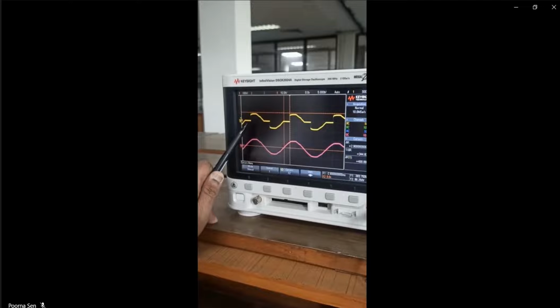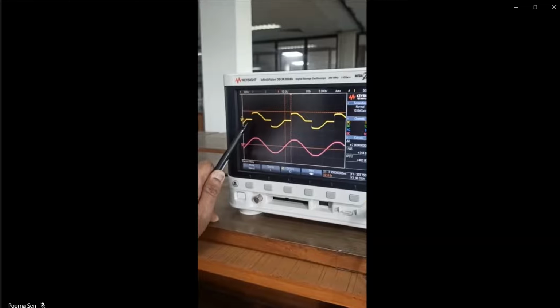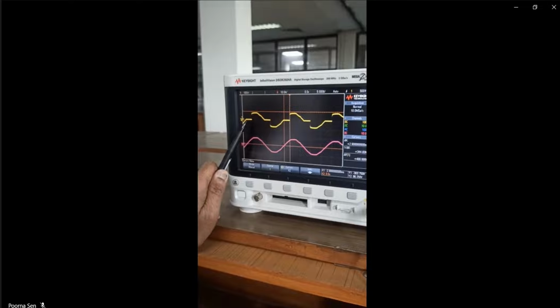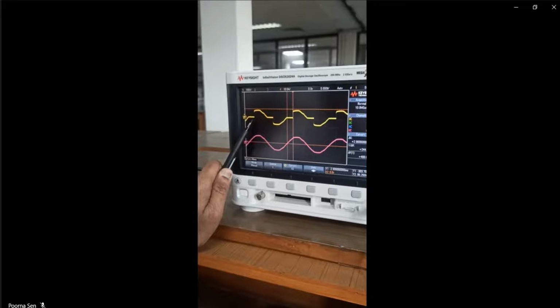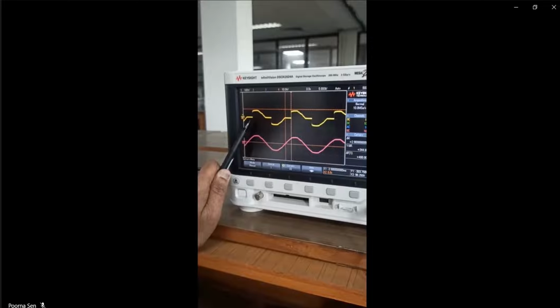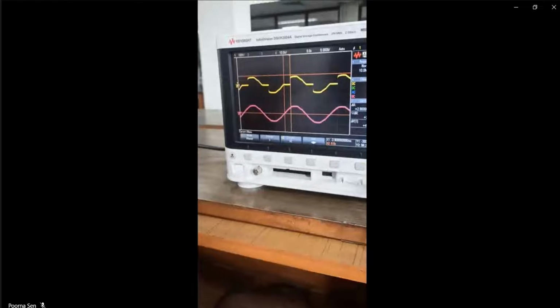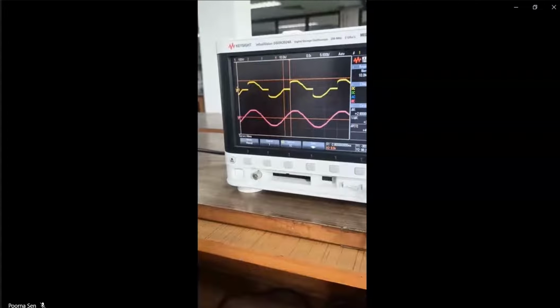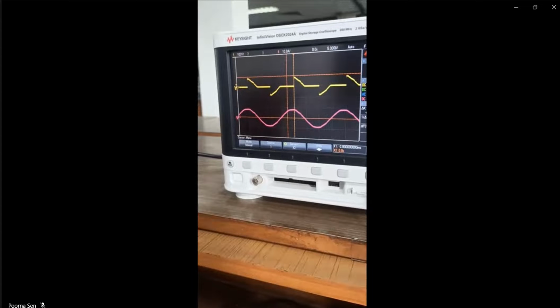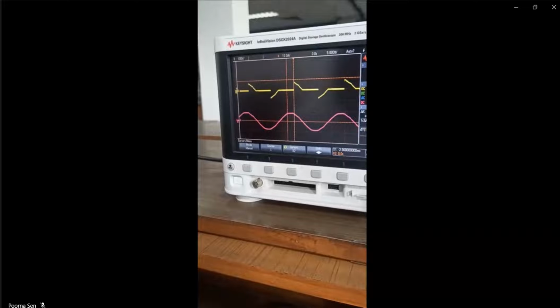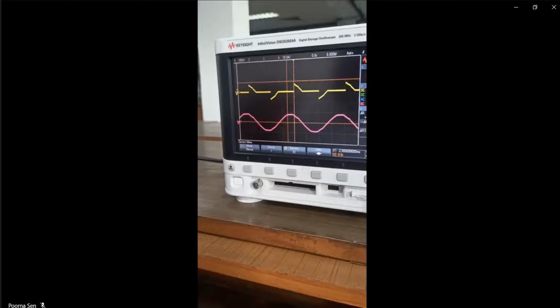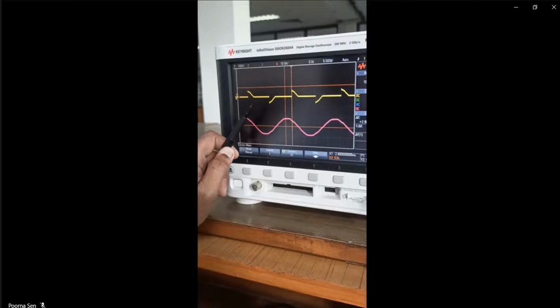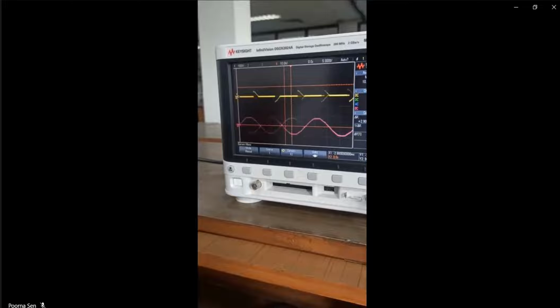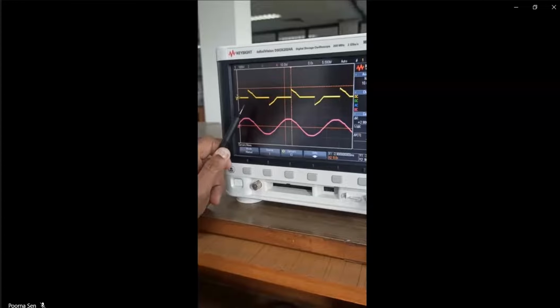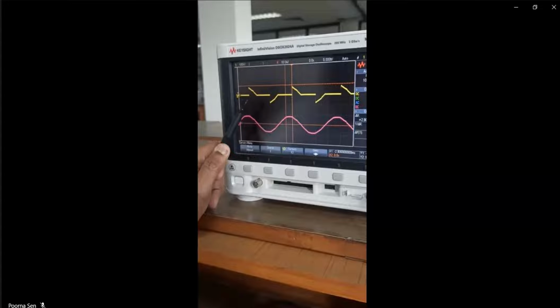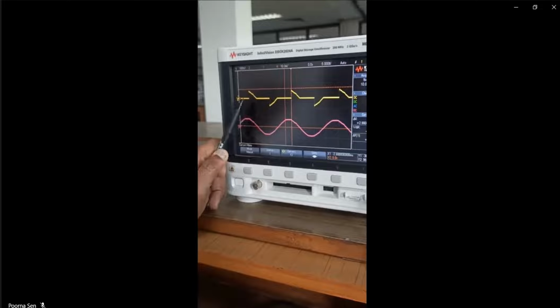So now I will adjust the firing angle and show you how the load voltage is going to reduce. At this moment the firing angle is close to 45 degrees. Now I will change the firing angle to more than 90 degrees. You can see that the firing angle is now more than 90 degrees, close to 120 degrees. If you look at the yellow trace, that is the load voltage.